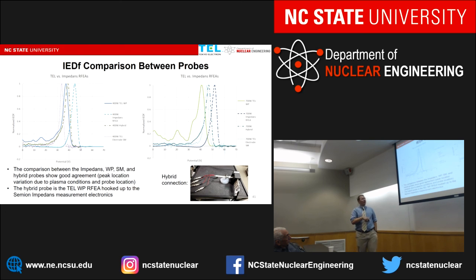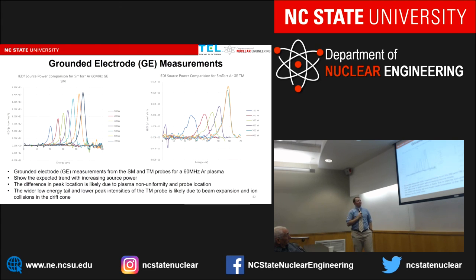In general, they look pretty good and consistent, showing that our RFEAs, or the TEL RFEAs, were working properly. You can see that there is some slight difference between the shapes, but we also did this hybrid version where we took the electronics of the Semion probe and connected it to the probe. When you did that, you get quite a different shape in the IEDF as well, especially over here. It's more likely that it's either the electronics or the post-processing software in the Impedans probe that's giving it its smoother shape than what we are getting with our base measurement and our electronics.